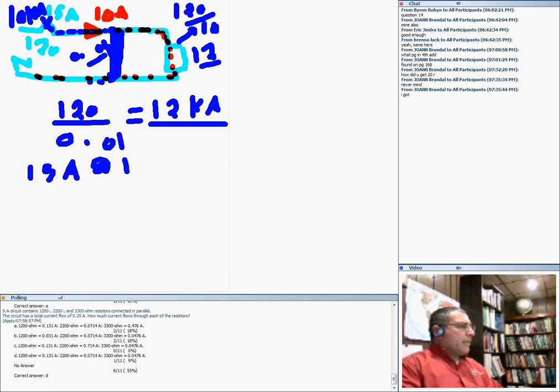And two, every circuit breaker has a rating — if you look at a 15 amp breaker, it's usually rated at 10K, meaning up to 10,000 amps it's capable of handling. If you pump more than 10,000 amps through it, you have just burned it. That's very important in a short circuit calculation.